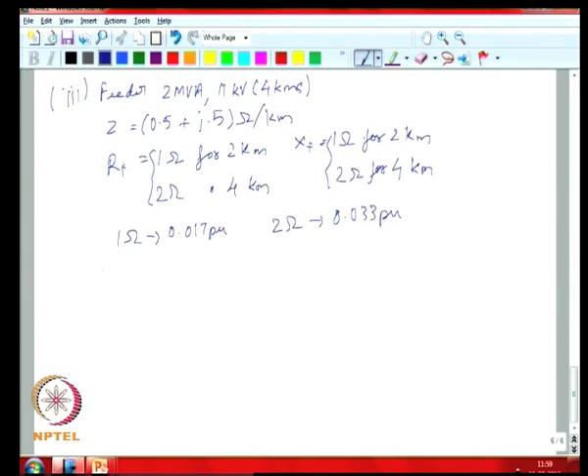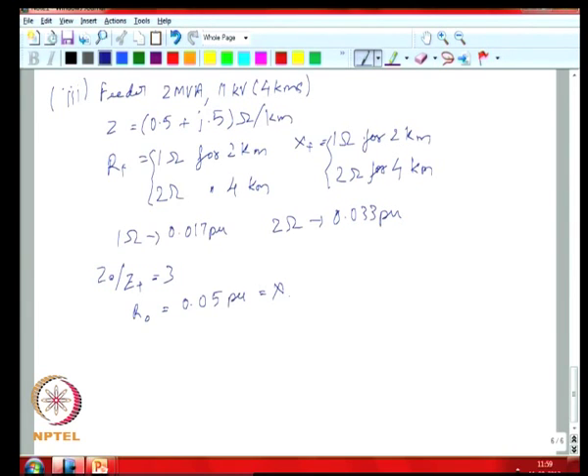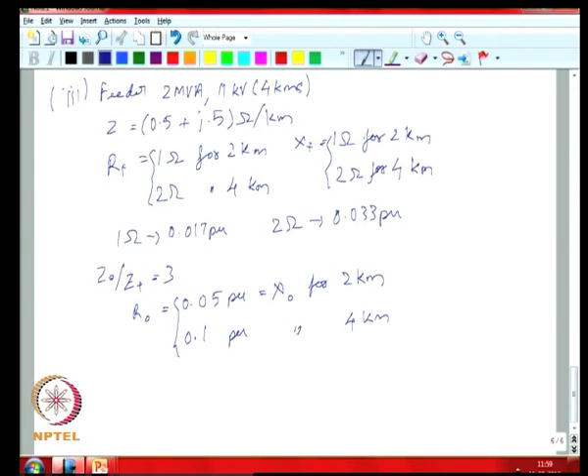You are also told that your z-0 divided by z-plus is 3. So you have R-0 equal to 0.05 per unit, which is also equal to your x-naught value for 2 kilometers, and 0.1 per unit for the 4-kilometer section. The next part of the problem is to draw a single-line diagram on the common base. Now that you have all parts of your problem on a common base, you can do that.